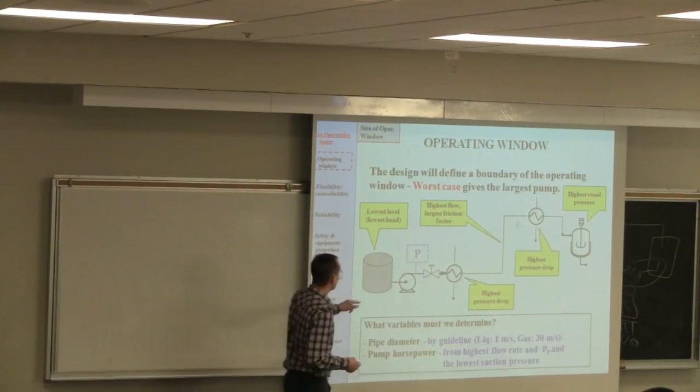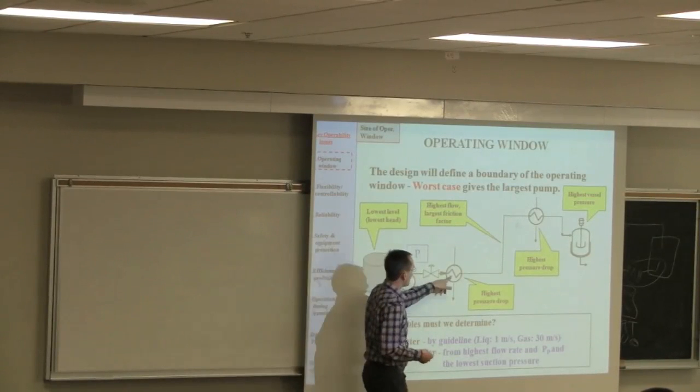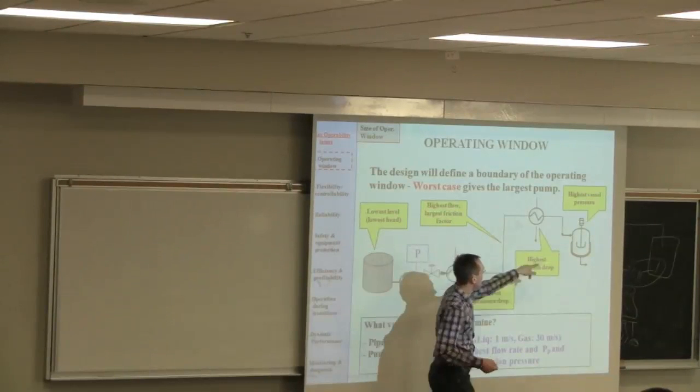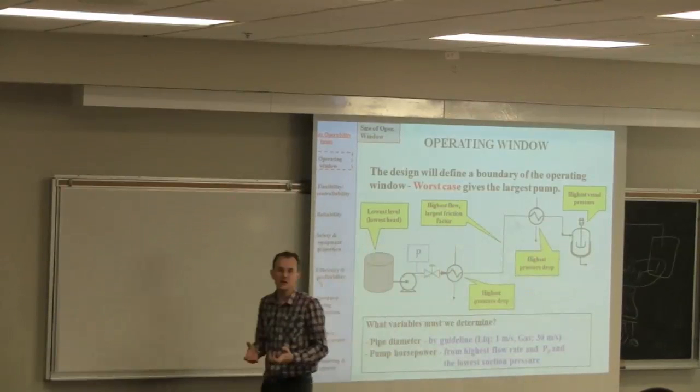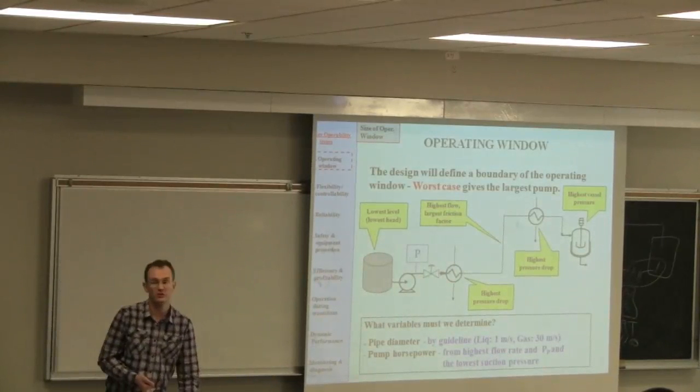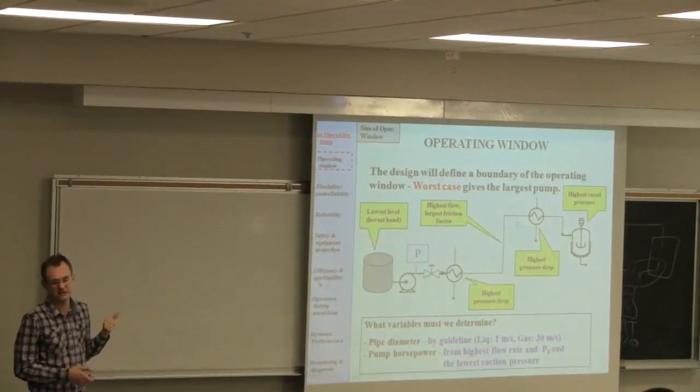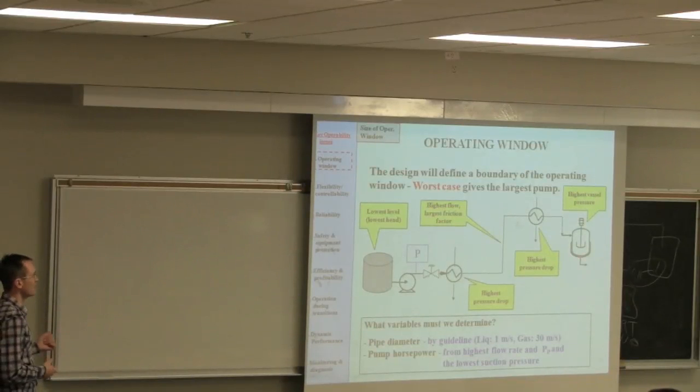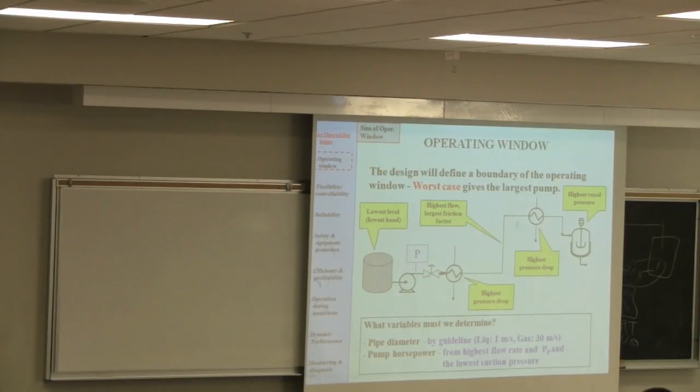So all of those give us an idea of the operating window of the process. We could design this pump so that it operates under very high tank level and low tank level, high pressure drops and low pressure drops through this piping, and high pressure and low pressure in that vessel. But it's clear that if we design it for the worst case, it's going to work for the other combinations as well. That's usually the approach we follow. So identify the variables that could change over the process. That goes back to the class about two, three weeks back, where we looked at different ways the process experiences disturbances.